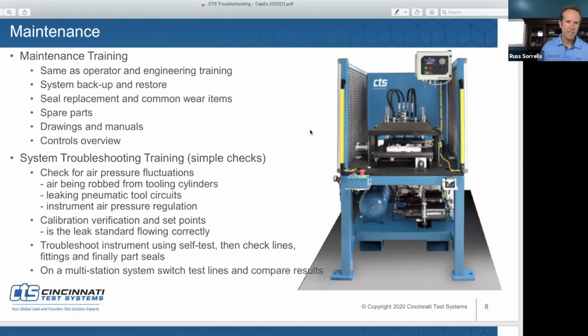Absolutely. The first thing, when a customer first gets an instrument, or if I'm working with a customer to train them, I say the very first thing you do when an operator says this instrument's messed up or there's a problem is put that self-test cap in and perform a self-test. And then if the self-test comes back good, now you can begin the troubleshooting process. It eliminates so much headache if it is the instrument, if debris got in the manifold. And that's the most common problem that we see, of course: debris gets into the manifold and it's not allowing the valves to seal properly. So we have what we call an internal leak inside the instrument, and the valve needs to be essentially rebuilt or the manifold swapped out.